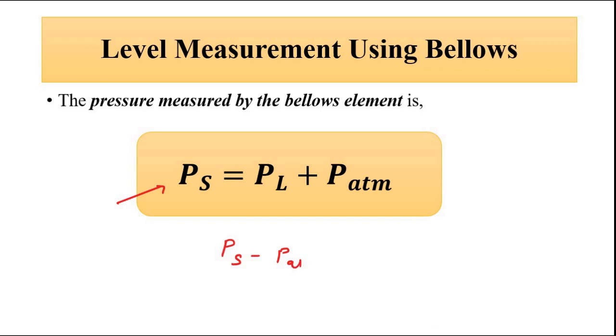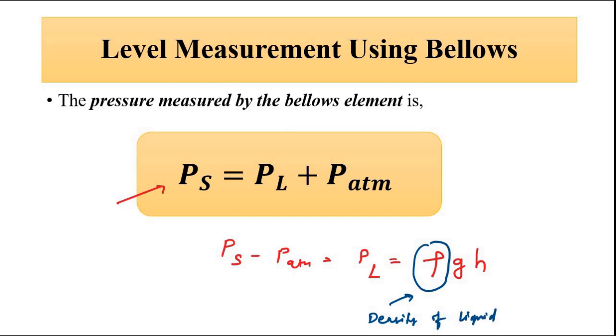So we subtract PS minus P atmospheric, which gives us the liquid column pressure, equal to rho g h. The important condition here is that the density of that particular liquid, the level of which we are measuring, must be known to us. Without this, there will be two unknowns in this equation and we cannot solve it.